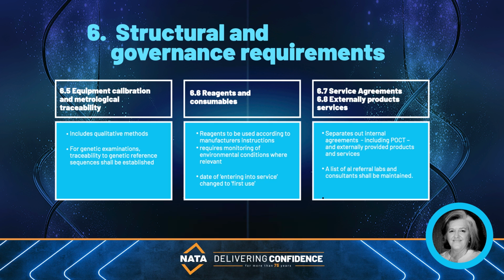For genetic examinations, traceability to genetic reference sequences shall be established. This is a new requirement that will need to be worked through. Qualitative and quantitative methods that measure characteristics rather than discrete analytes shall specify the characteristic being addressed and the requirements for reproducibility of these over time.